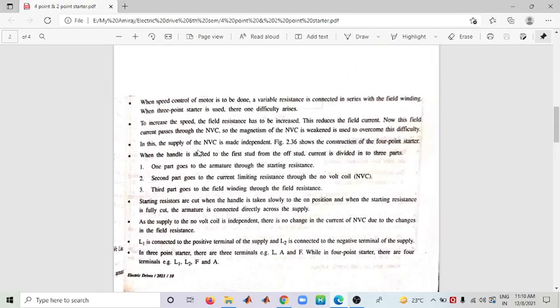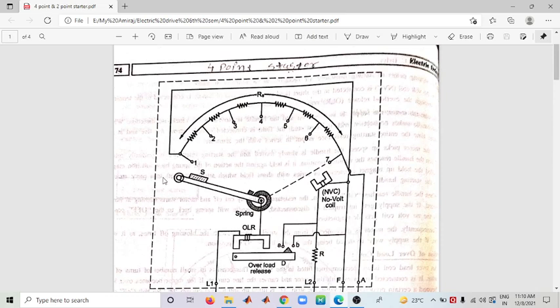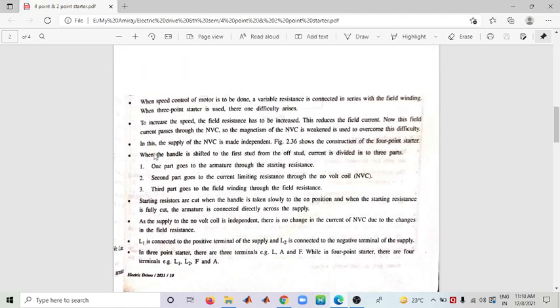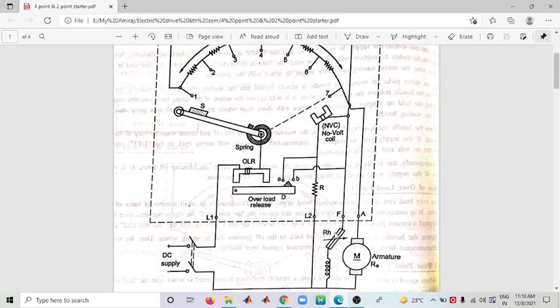In the Four Point Starter, the incoming current is divided into three parts. The first part goes to the armature through the starting resistance. The second part goes through the current limiting resistance to the NVC (No Volt Coil). The third part goes to the field through the field resistance and variable resistance.